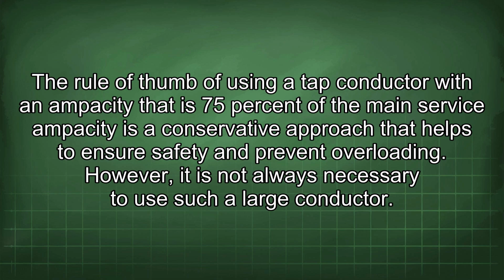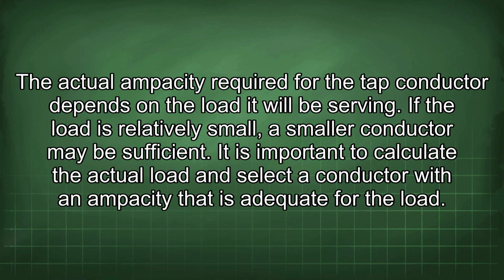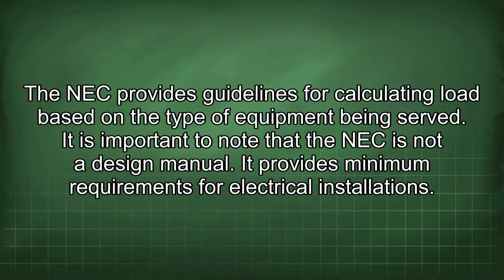However, it is not always necessary to use such a large conductor. The actual ampacity required for the tap conductor depends on the load it will be serving. If the load is relatively small, a smaller conductor may be sufficient. It is important to calculate the actual load and select a conductor with an ampacity that is adequate for the load. The NEC provides guidelines for calculating load based on the type of equipment being served.